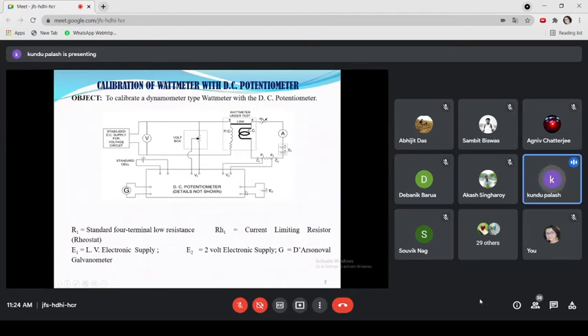So the wire current should be varied, which means by adjusting the potentiometer wire current, the voltage is accurately set to that of the standard cell. This process is called the standardization of the potentiometer before use in the laboratory. Then there is no further use of the standard cell, so it will be isolated. After standardization, the two unknown voltages are measured with the help of the DC potentiometer. These are the methods.